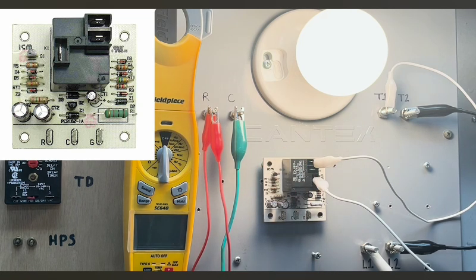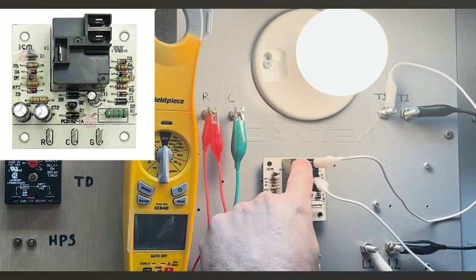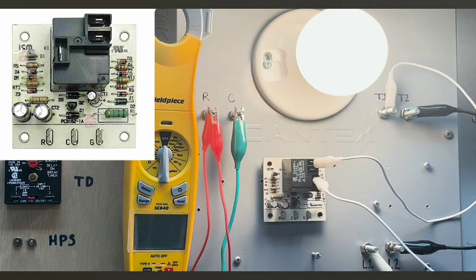We're going to go ahead and take this over to the smart board in a minute, and I'm going to wire this up. But first, before we do that, we want to go ahead and put this on its practical application. Let's go ahead and wire this up to a blower motor. I'm going to go ahead and take the liberty and take this contact up here. I'm going to wire it to a light bulb. So I'll have the fan motor wired to normally open. I'll have the light bulb wired to normally closed. And then we can see this relay toggle between those two with that delay in a more practical application.